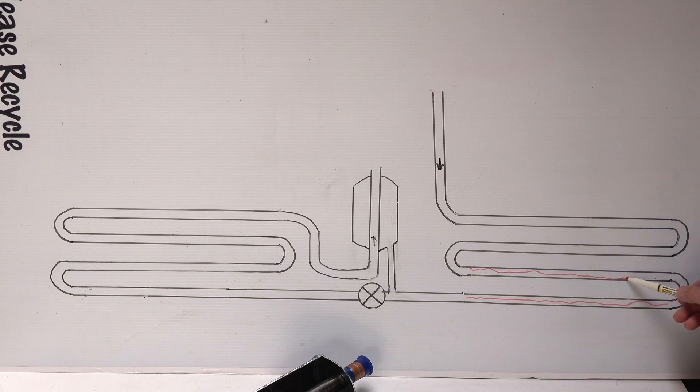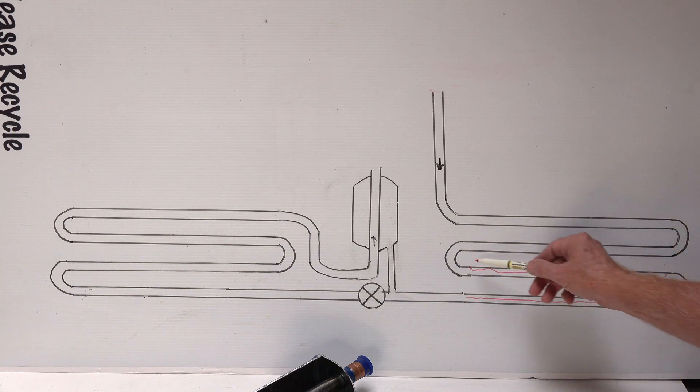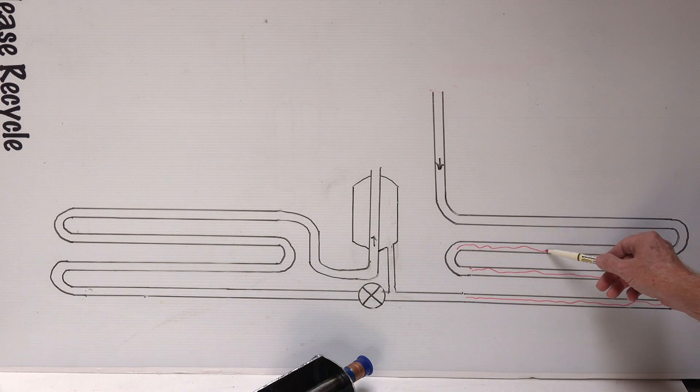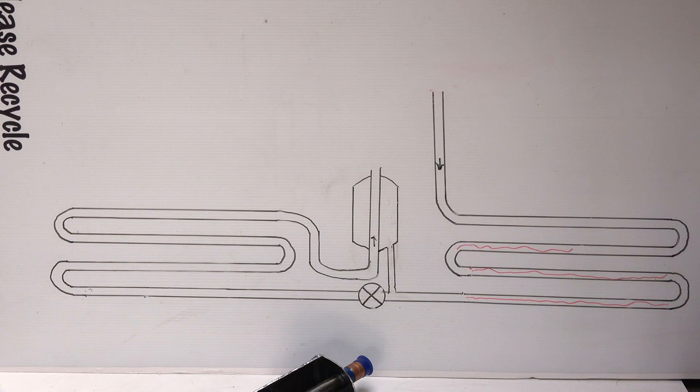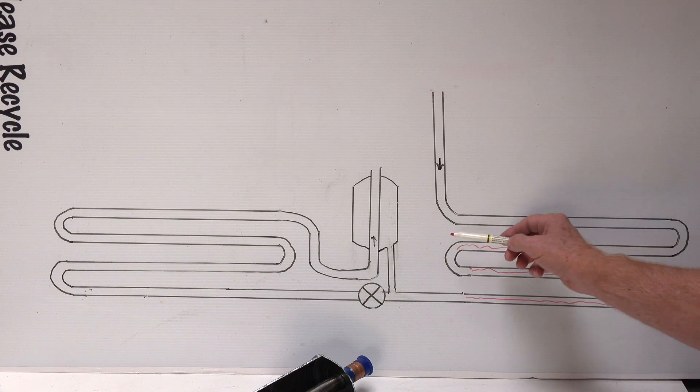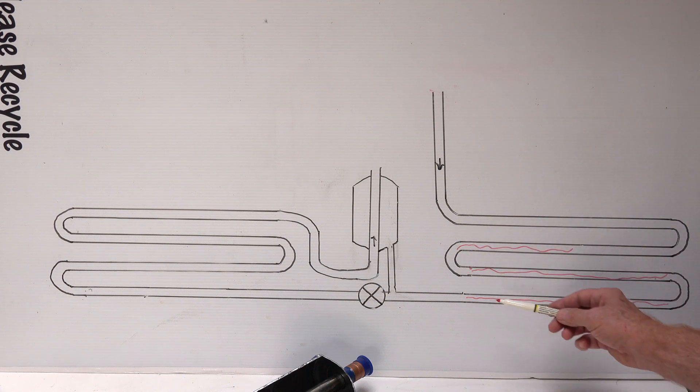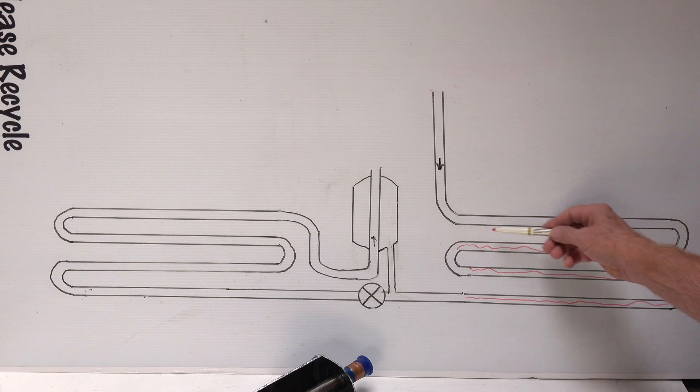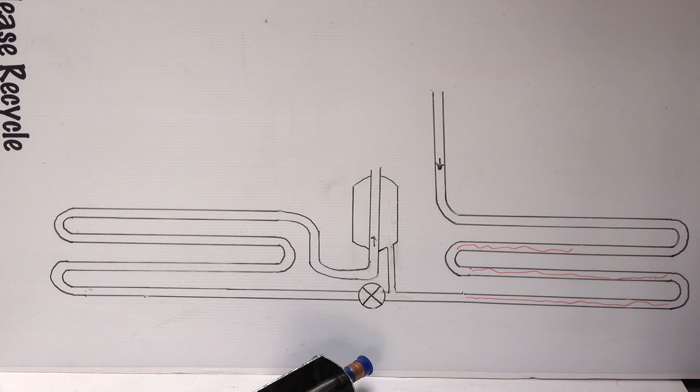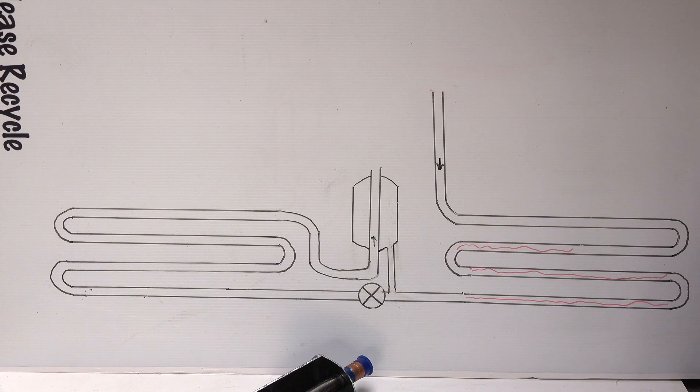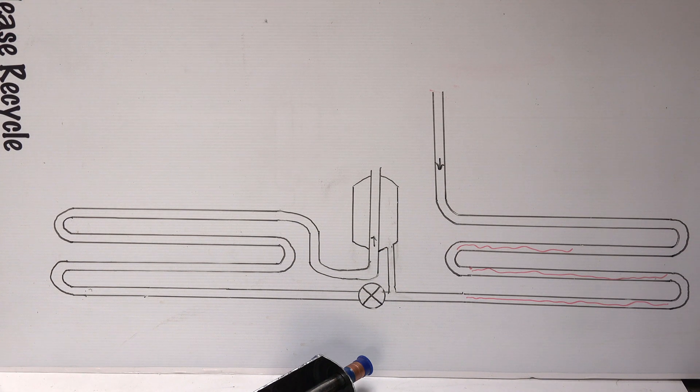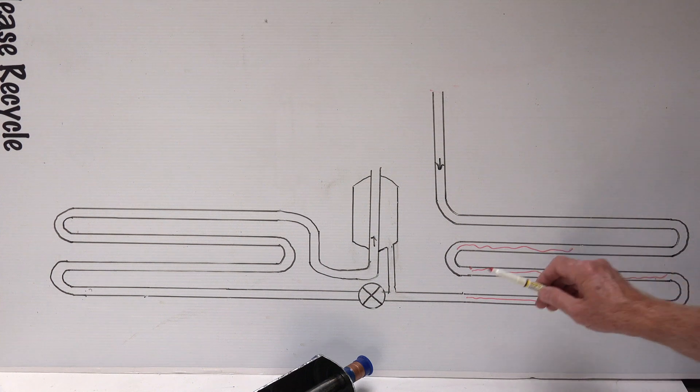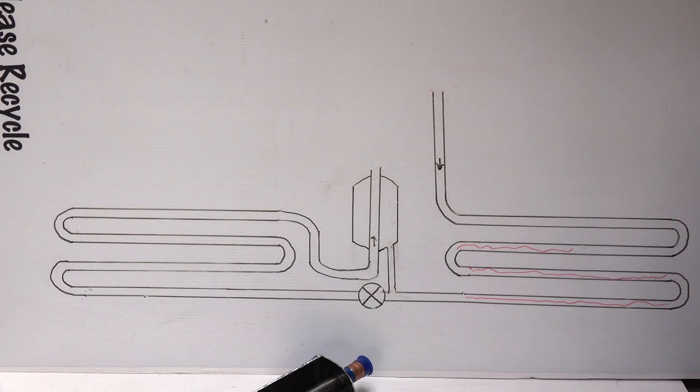That's because instead of having say liquid refrigerant here, we've also got it up here and maybe even up into here. So with all this liquid refrigerant, I have very little area to condense the refrigerant into a liquid. So we have too much liquid, it's going to back up behind that TXV.